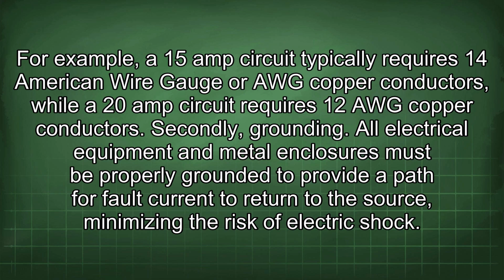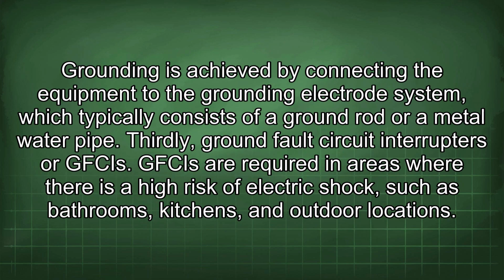Secondly, grounding. All electrical equipment and metal enclosures must be properly grounded to provide a path for fault current to return to the source, minimizing the risk of electric shock. Grounding is achieved by connecting the equipment to the grounding electrode system, which typically consists of a ground rod or a metal water pipe.